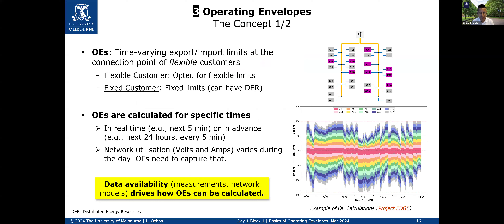An operating envelope is a time-varying export limit or import limit at the connection point of a flexible customer. This is important — 'at the connection point' — because this is how the AER, the Australian Energy Regulator, also considers the flexible export limit. The reality is that calculating this value at the connection point means you need to capture what is happening behind the meter — not just the photovoltaics or potential battery used for services, but also the demand. Doing that is not simple at all.